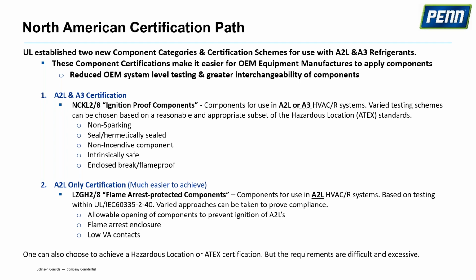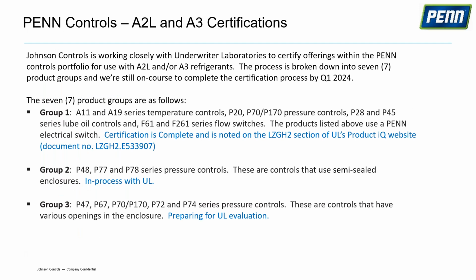But right now we are focused on NCKL2 and LZGH2 certifications. So moving on, we sent a letter to our OEM customers in April letting them know we started working closely with UL. We had a series of reviews with UL in 2022, and right now we're proud to say that our Group 1, which includes our A11 and A19 series temperature controls, some of our pressure controls including P20 adjustable, P70, P170, our oil and lube oil controls, and our flow switches, are now all through the certification process. That certification is LZGH2, so they're suitable for use with A2L refrigerants.